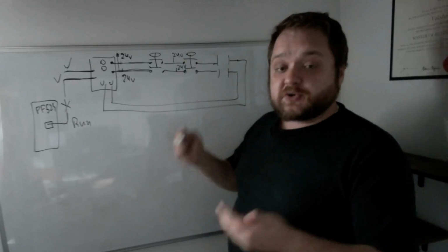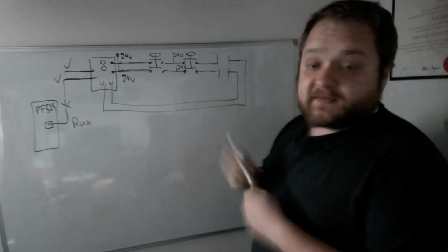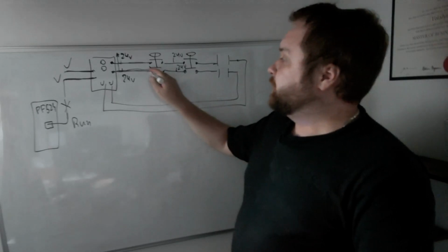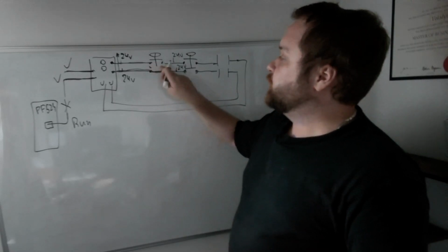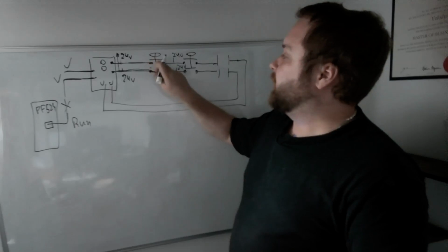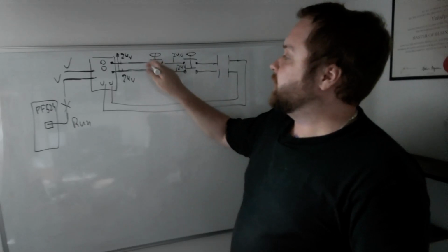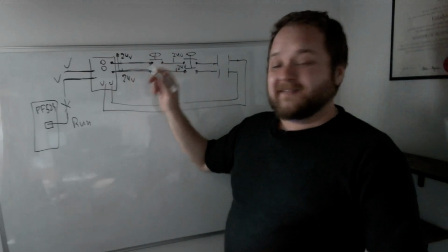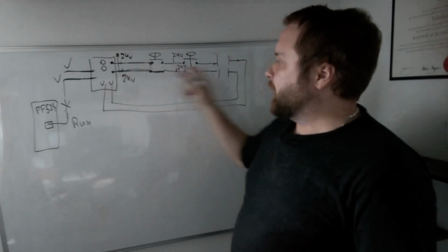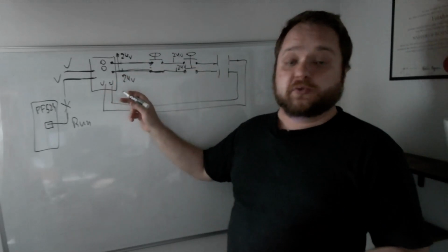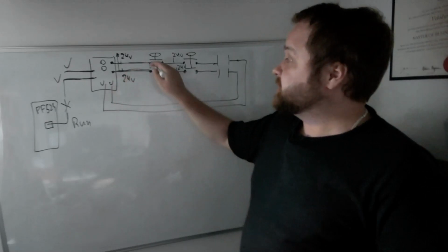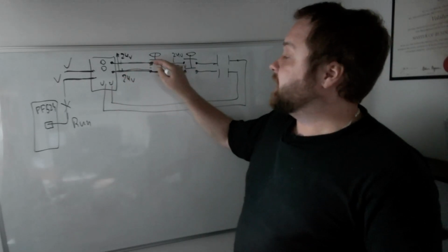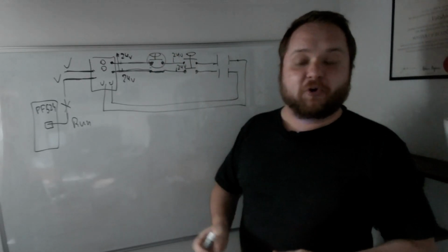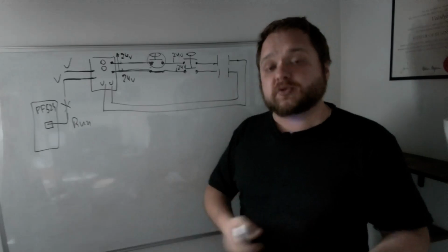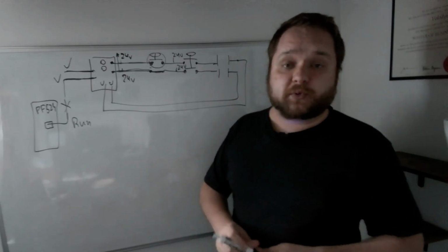So it is important not to create scenarios where, for example, and I've seen this done in plants, where they would bypass one of the channels, and this would be basically a normal push button that is not e-stop dual channel rated. And so, of course, a very simple relay is going to allow both of those 24 volt channels to go through. It will satisfy the conditions, but if something were to happen and this button were to fail, you're going to be in a lot of trouble, not only in terms of damaging equipment, but also potentially putting or having put personnel at risk.